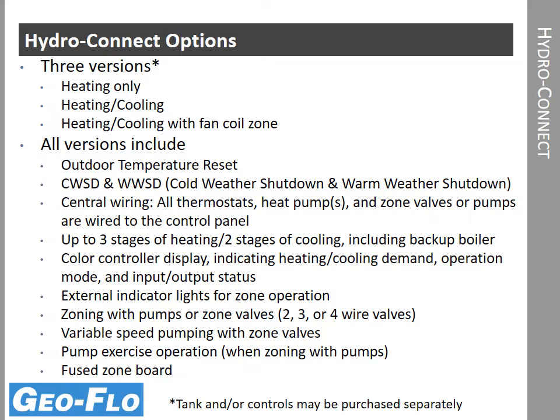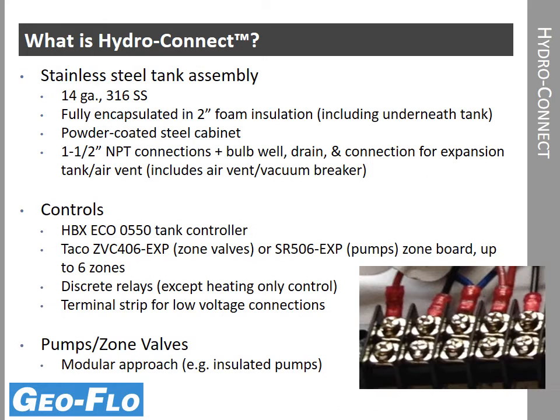The pump exercise option is for zoning with pumps. It occasionally energizes the pump so that if it's a heating only system, for example, those pumps don't seize up if they're sitting idle for a long period of time. And the zone board does have fusing available. So a lot of features with all 3 of the versions. Let's take a look at the components that make up HydroConnect.